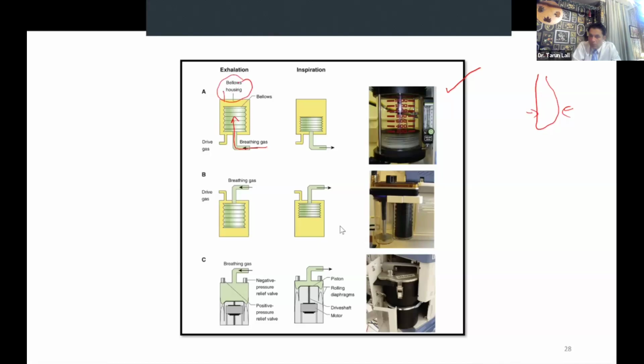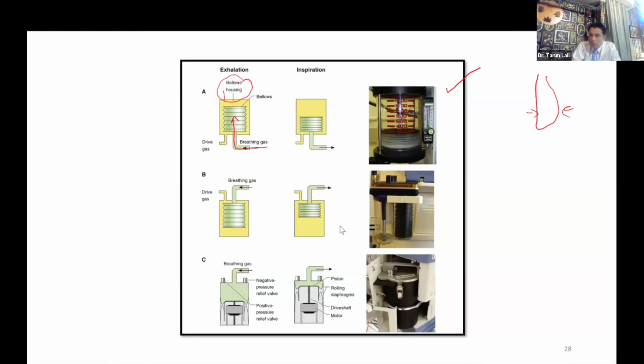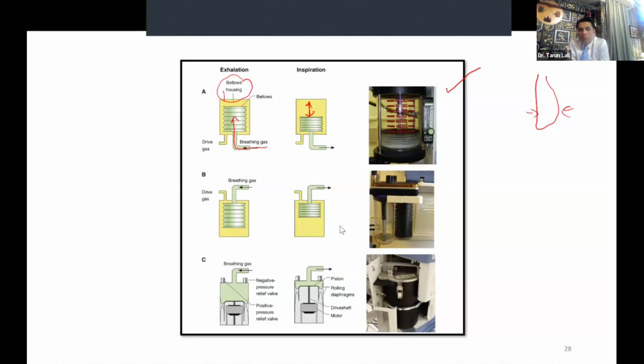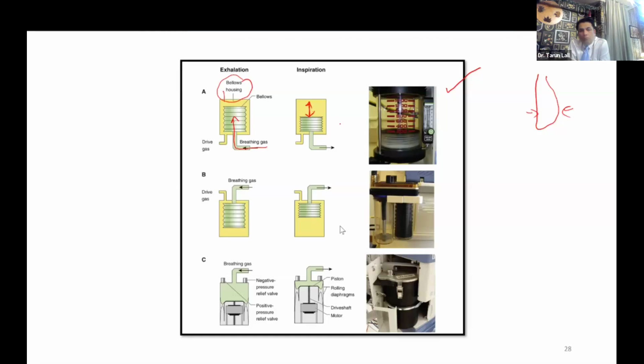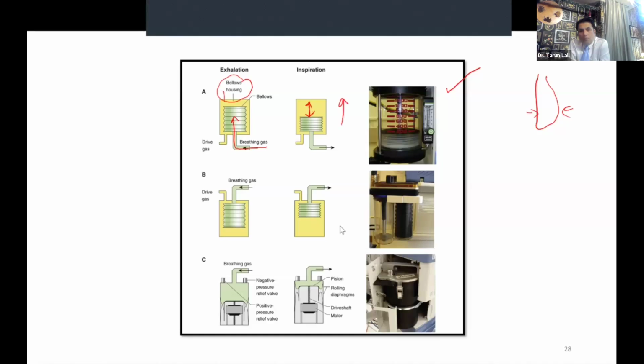At whatever rate and whatever tidal volume I have set, the computer decides and pushes in driving gas. This driving gas is oxygen at gas pipeline pressure, that is 40 to 60 psi. So this chamber, the space outside the bellows, quickly fills up with the driving gas, which leads to the bellows moving down. And that is how your ventilation is achieved. Then as the patient exhales, the bellows fills up once again and it goes up. So we call it ascending bellows.